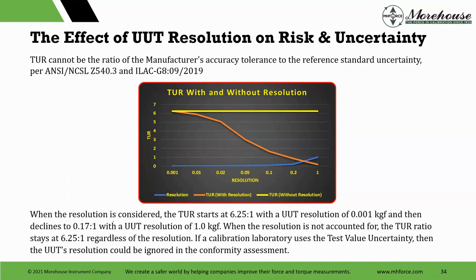When the resolution is considered, the TUR starts at 6.25 with the UUT resolution of 0.001 kgf and then declines to 0.17 to 1 with a UUT resolution of 1 kilogram of force. So when resolution is not accounted for, the TUR ratio stays at 6.25 regardless of the resolution. If a calibration laboratory uses something like test value uncertainty, which is in another standard, then the UUT's resolution could be ignored in the conformity assessment. Just a risk. In fact, I mentioned the paper Scott Mims wrote. It's about the importance of decisions, and he uses a micrometer example in there. This is our example from a load cell.